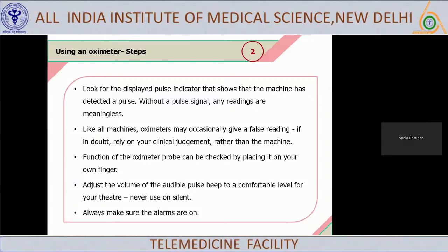First, the function of the oximeter probe can be checked by placing it on your own finger, because you know that your saturation is okay. So that will be a self-test. Adjust the volume of the audible pulse beep. Now, this is important, especially when you are inside the hospital setting. Each pulse oximeter has an alarm setting. So please set it up, because in case the patient deteriorates, the alarm can warn you that the saturation is falling or the pulse is falling, and you can take appropriate action.